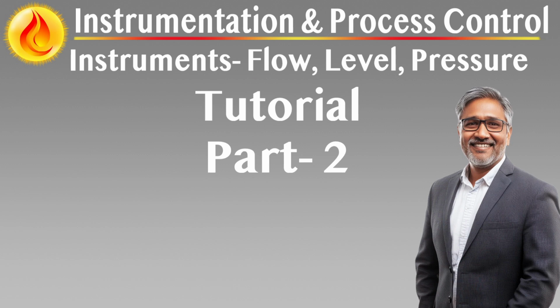Visual coding for functional clarity. All IPF trip initiators, CL1 or higher, must feature a red finish to distinguish them from standard process instruments. Instruments in oxygen service must be finished in yellow per safety marking standards. All other plant-mounted instruments may follow the manufacturer's standard color, with red and yellow excluded to avoid confusion with safety-critical devices. Compliance with pressure boundary integrity.